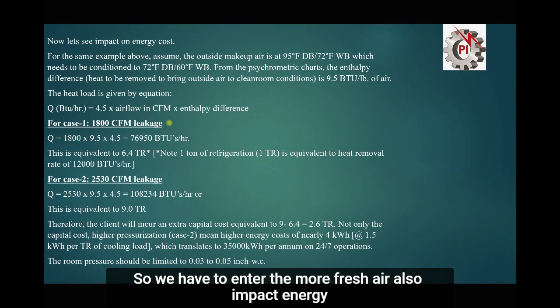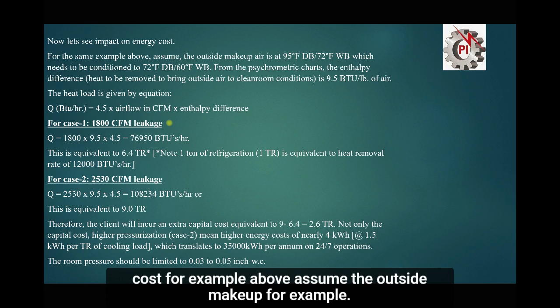Now let's see the impact on energy cost. For the same example above, assume the outside makeup air is at a temperature of 95 dry bulb and 72 wet bulb, which needs to be conditioned to 72 dry bulb and 60 wet bulb. This is our requirement. From the psychrometric chart we can find the enthalpy. First we find the enthalpy at the outside temperature, and then we find the enthalpy at the required temperature we need to maintain in the room.